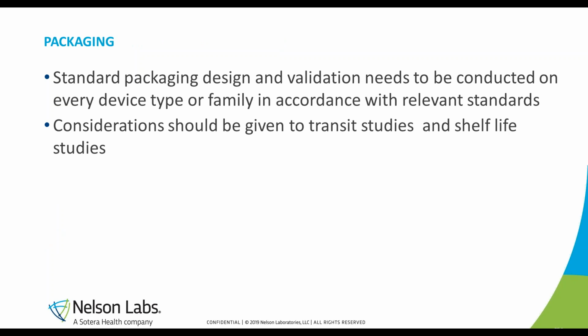Packaging of reprocessed medical devices will need to be considered as well. Standard packaging design and validation should be conducted on every device type and/or product family. It is not uncommon for a third-party entity to follow packaging configurations previously developed by the original manufacturer. If sterile, the packaging design and validation will need to be conducted in accordance with relevant standards such as ISO 11607 for considerations given to transportation and shelf life studies.